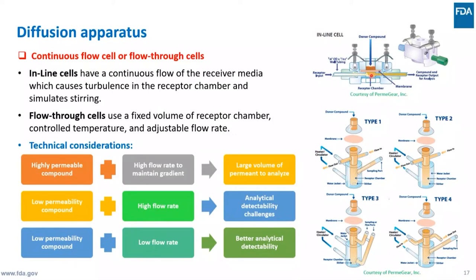The flow rate of the media is a critical parameter as it significantly affects flux. For highly permeable drugs with high flow rate, large volumes are collected which may cause analytical detectability problems. For low permeability compounds with high flow rate, analytical detectability is also a problem due to massive dilution. For low permeability drugs with low flow rate, better detectability may be achieved but saturation of the tangential layer may occur, meaning the flow rate is insufficient to clear the tangential diffusion layer behind the membrane. Optimization of diffusion settings is important for consistent results.